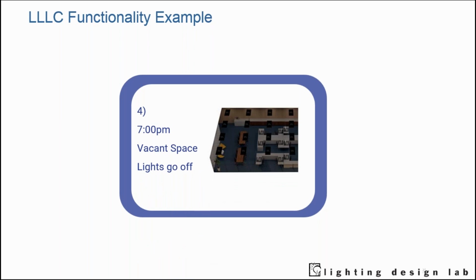The best part is most luminaire level lighting control fixtures operate this way by default. They'll have this controls resilience, or default way to operate, that gives you the majority of the control strategies you need without you even having to pull out your commissioning tool to make them act this way.